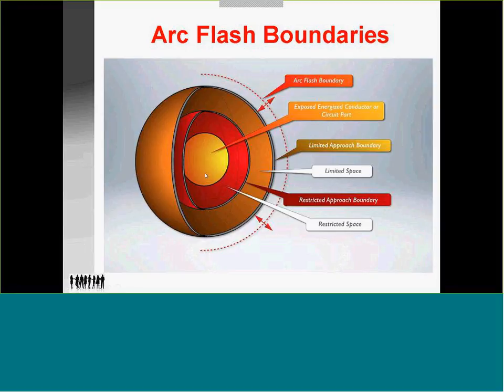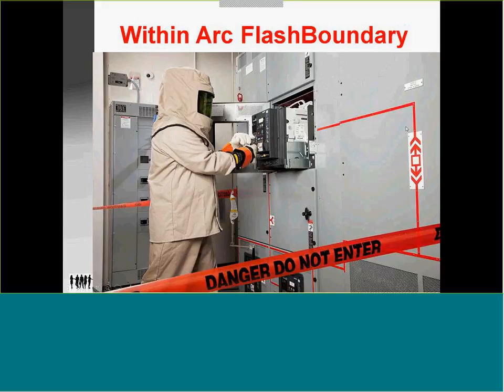So the further away you get, the heat actually diminishes as it's going upward. In a cycle like this, you have your exposed energized conductor or circuit part. Then the restricted boundary, which would be the 12-inch. The limited approach boundary, which will be 42 inches. But here the arc flash boundary is greater, therefore this boundary must now be extended to this area, then the physical barrier. Here is where they're doing a category 4, which is 40 calories. They're pulling a bucket out to do some work on it while energized.